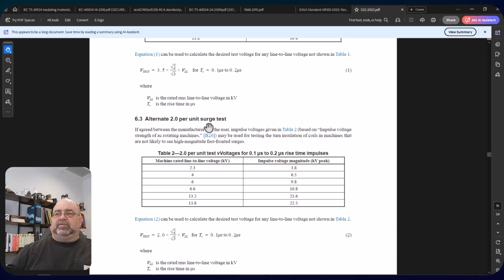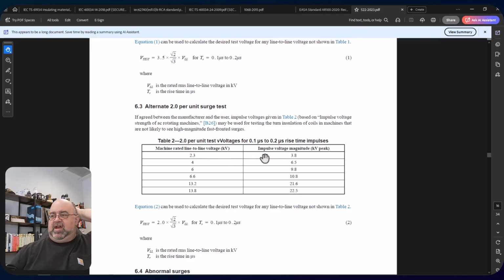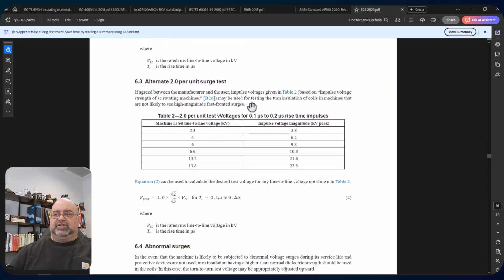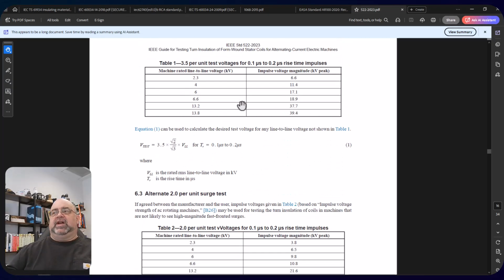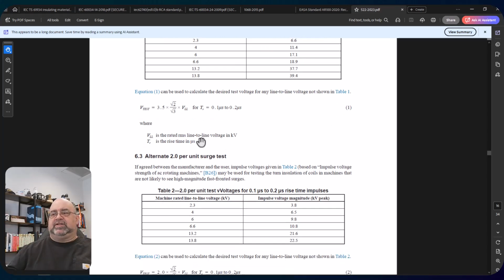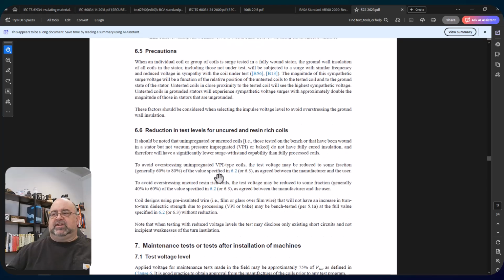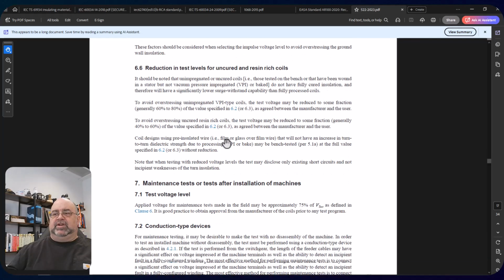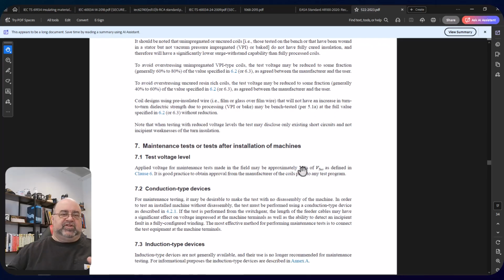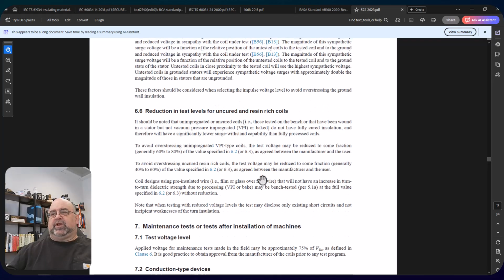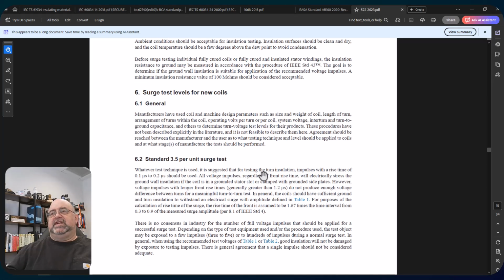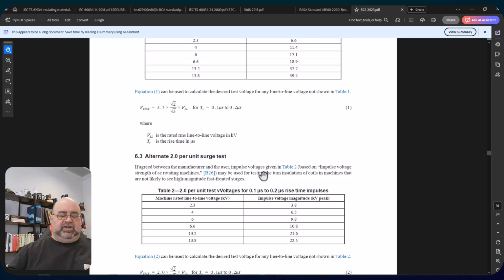Calculation for that, 2 per unit surge test. This one here is a lower application, so this would be machines that are not going to see fast closing and stuff like this. The idea behind the surge test is the withstand should cover circuit bounce and other things that could cause breakdown of insulation. This would be for soft starts, and then how to reduce that. If it's a machine in the field, you do 75% of whatever that value is. We used to use twice the voltage plus 1,000. I have not seen that in a little while here. It's often still used as a rule of thumb.